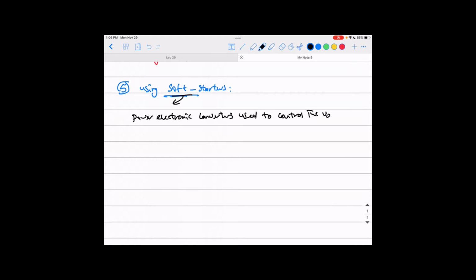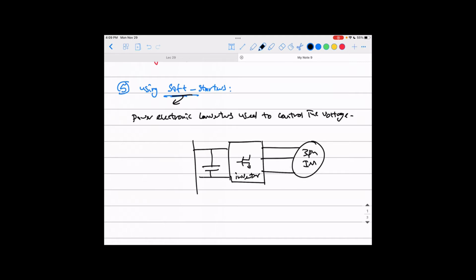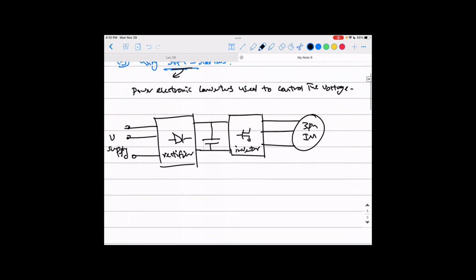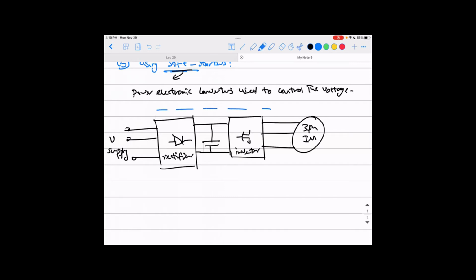control the voltage. Okay, so rather than just having an auto transformer or other stuff to control our voltage to reduce it at the beginning, we can actually go with power electronics. Remember we talked about variable speed drives or V over F speed control of three-phase induction motor. So that is our three-phase induction motor, and rather than connecting directly to the supply, we use our power electronics again. So here is an inverter, and here is your DC link capacitor, and there is another converter which is basically a rectifier, and here is your supply, V supply. Remember we used the same thing before to control the frequency and voltage of the motor. We're here not concerned about controlling the frequency anymore. We just use this power electronic stage here, and that is what we call a soft starter.